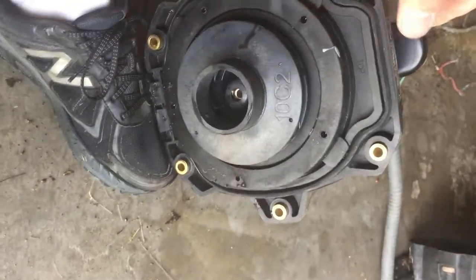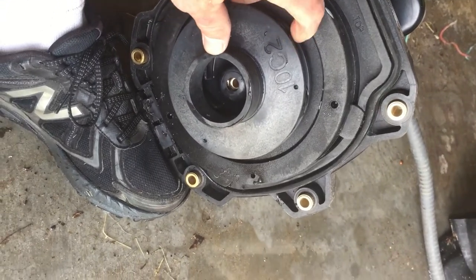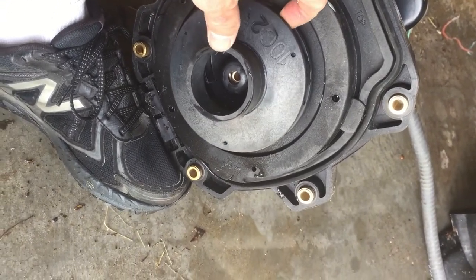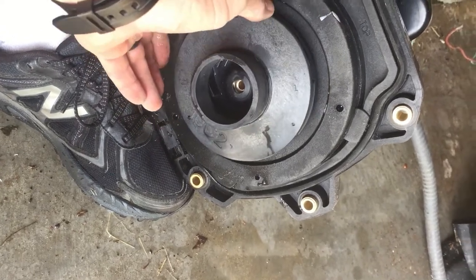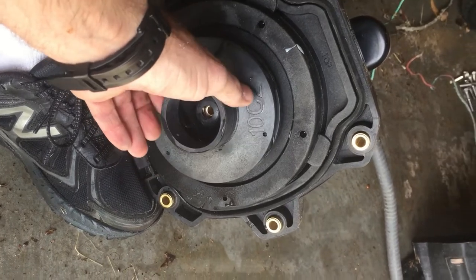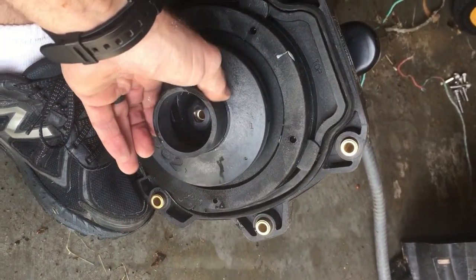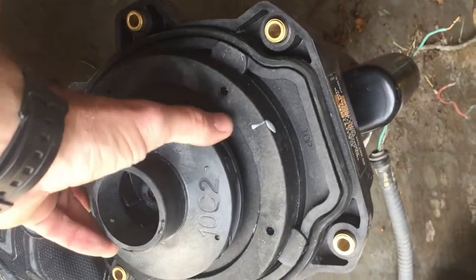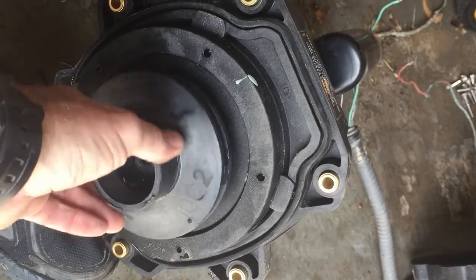Hold the shaft at the back — on the Hayward factory motors, it's a 7/16 to hold the back of the shaft so that you can turn this in a normal loosening direction. On A.O. Smith motors or Century motors, something like that, then it's usually a half inch to hold the shaft. I already popped this one loose and then just turned it in the loosening direction.